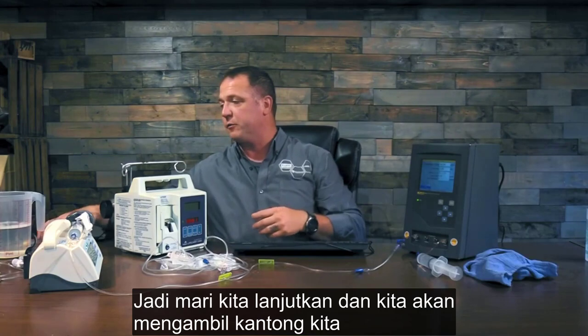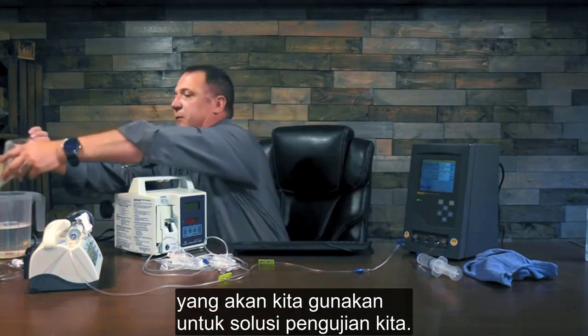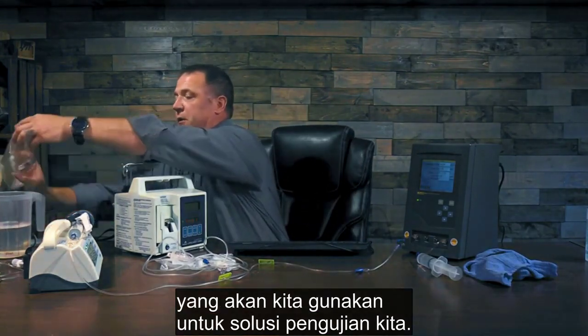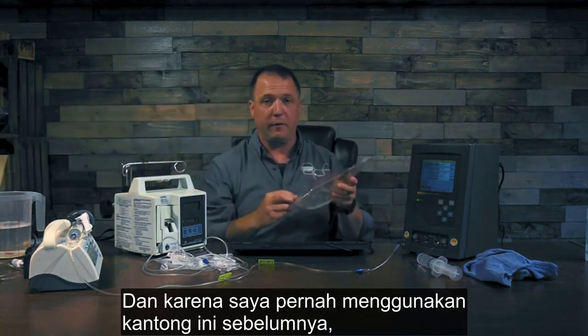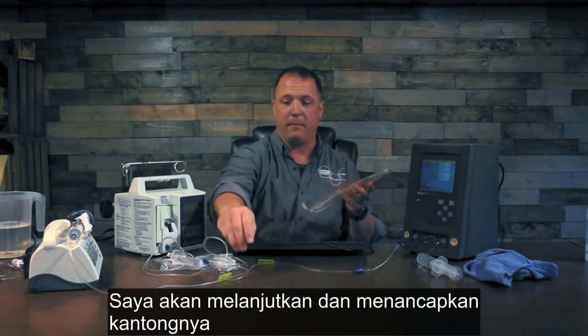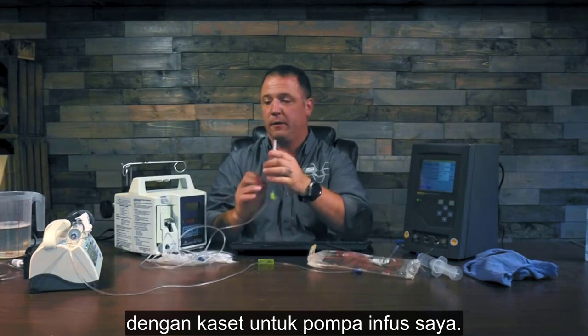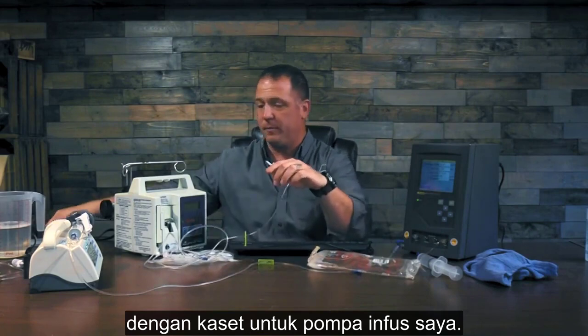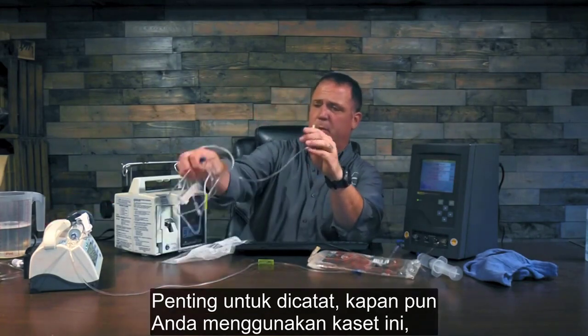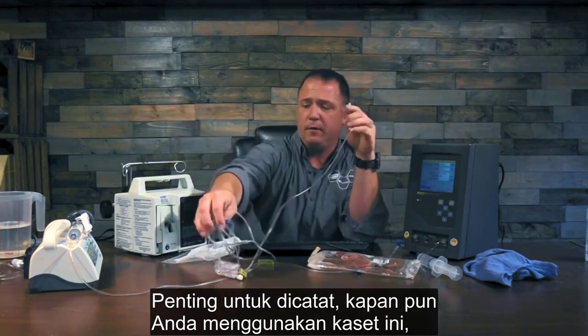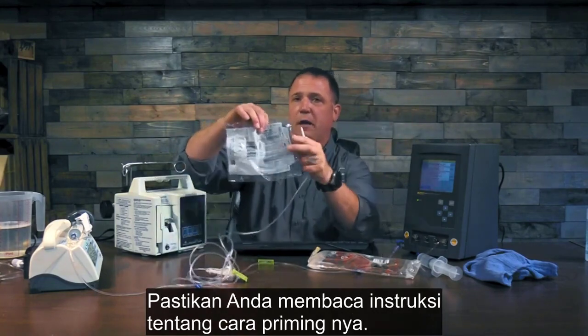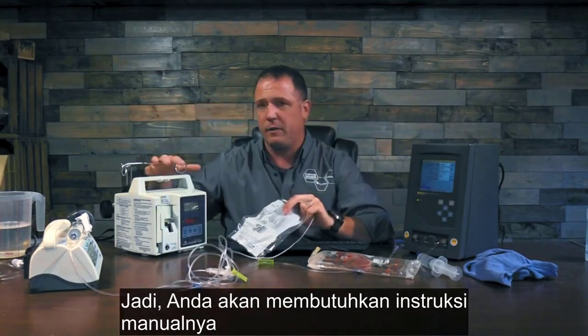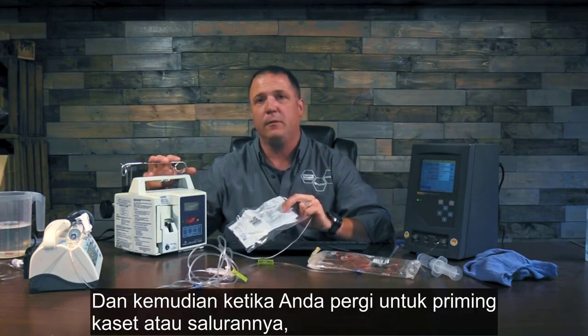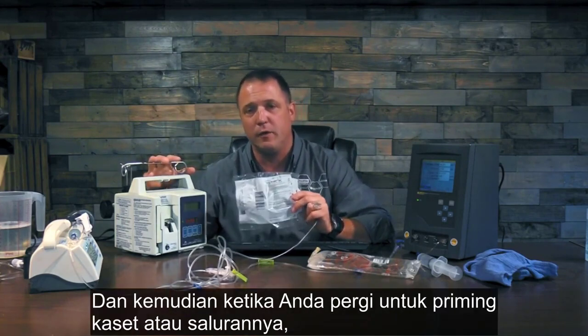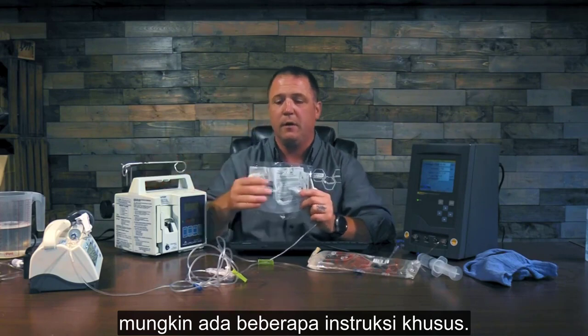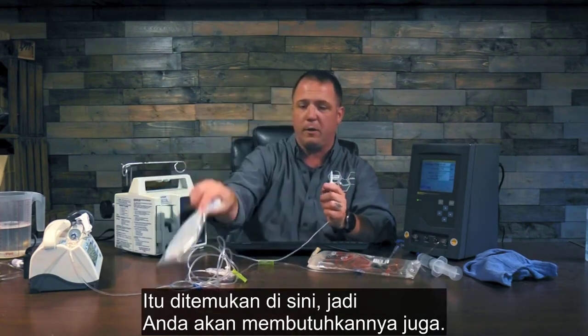So let's go ahead and we'll grab our bag that we're going to use for our test solution. And because I've used this bag before, I'm going to go ahead and spike the bag with a cassette for my infusion pump. It's important to note, whenever you use these cassettes, make sure you read the instructions on how to prime it. So you're going to need the instruction manual for your infusion pump. And then when you go to prime the cassette or the tubing, it might have some special instructions. It's found right here, so you're going to need those as well.